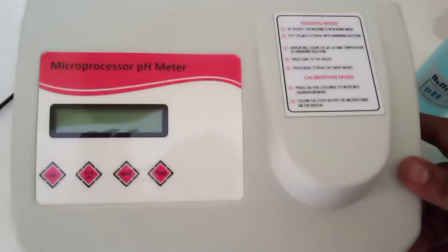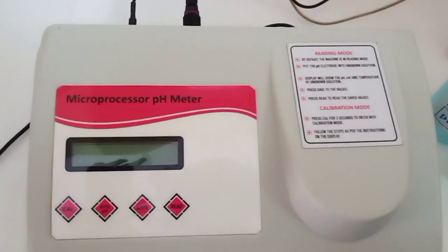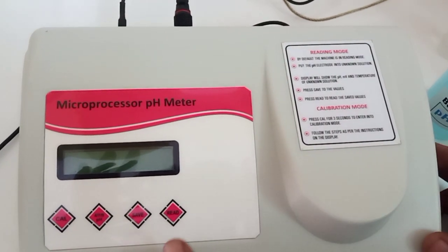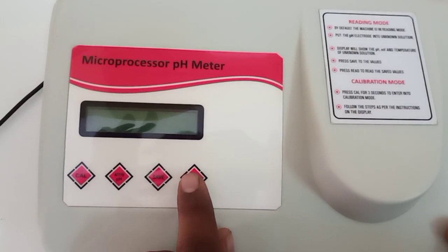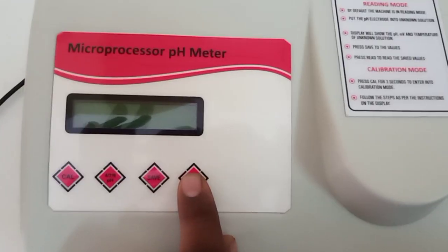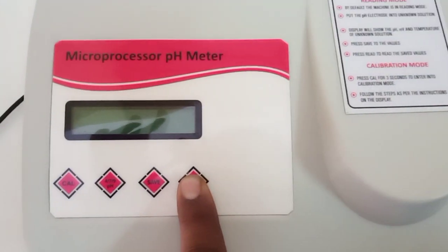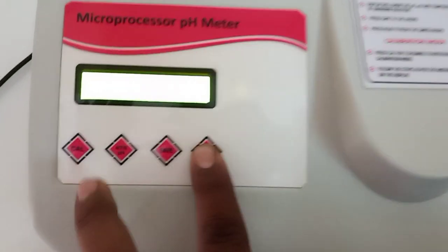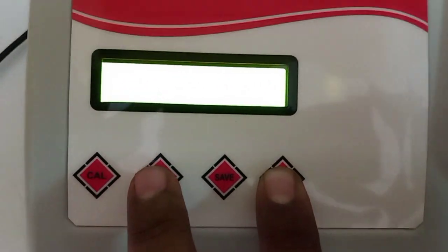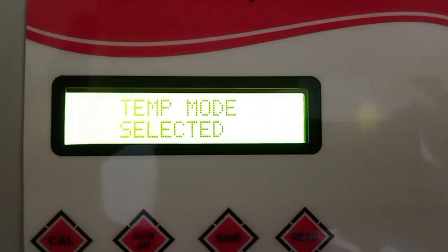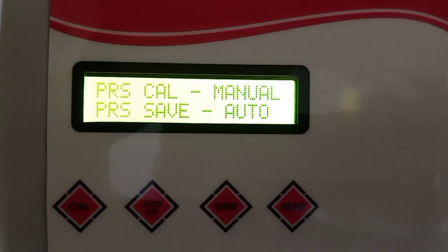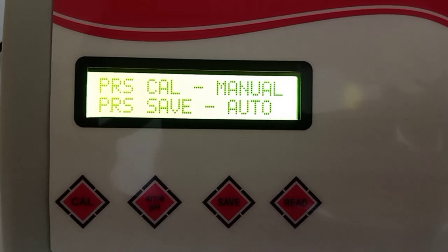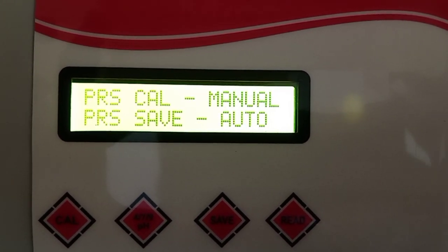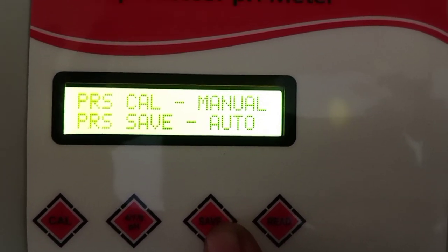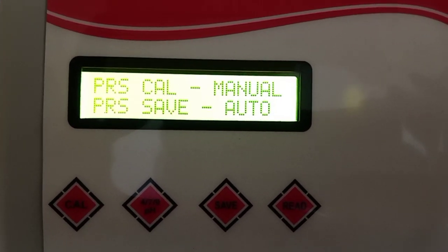Now we are going to perform some internal settings, like how to convert automatic temperature into manual temperature. For that, switch off the machine and press read button. Don't release the read button and switch on the machine. While pressing read button, press 4. Message shows temperature mode selected. Now if user wants to go for automatic temperature compensation, then press save. If you want to go for manual temperature compensation, press cal.